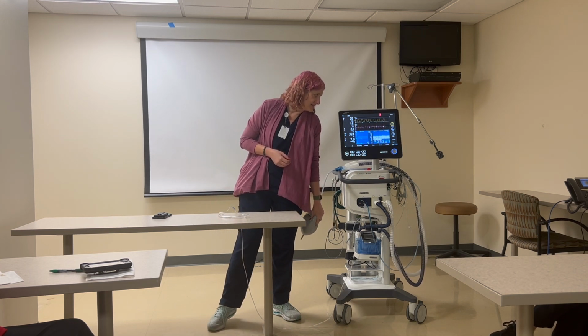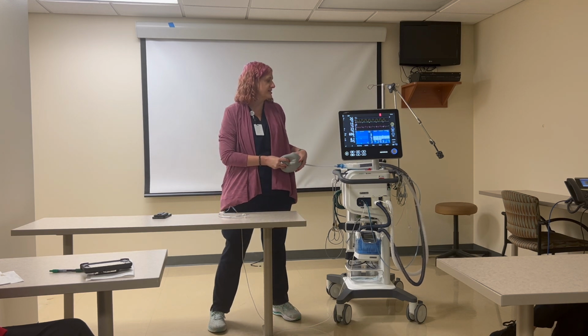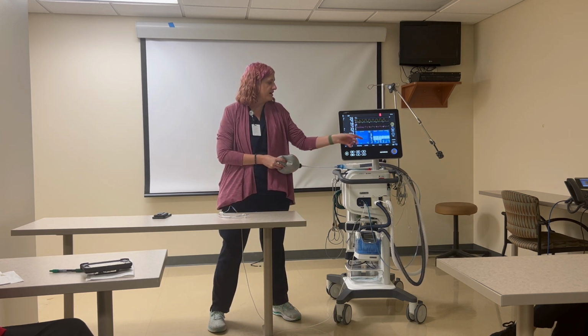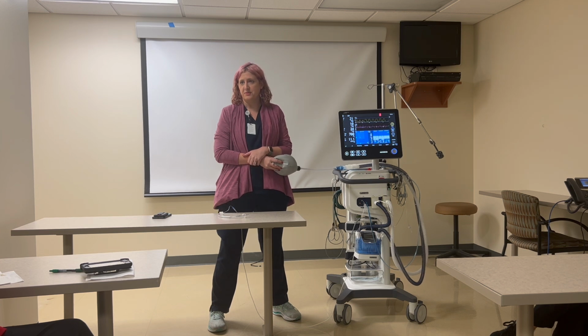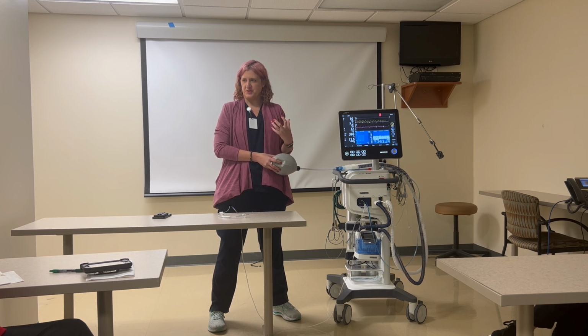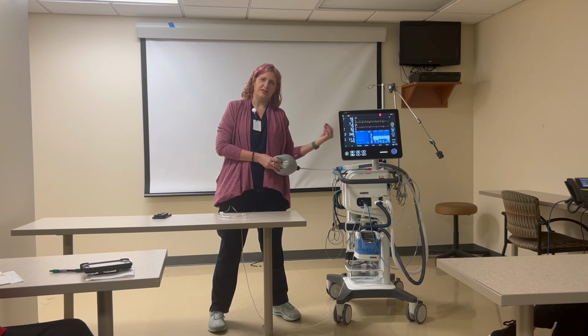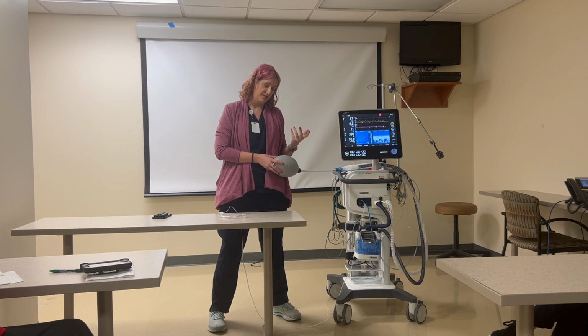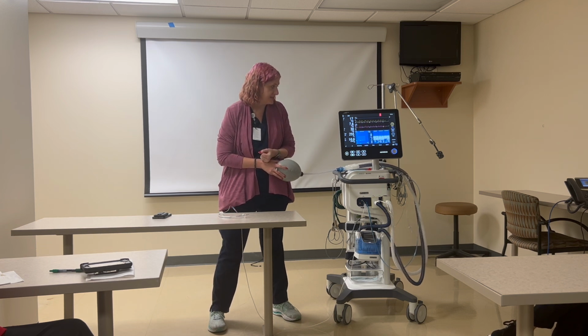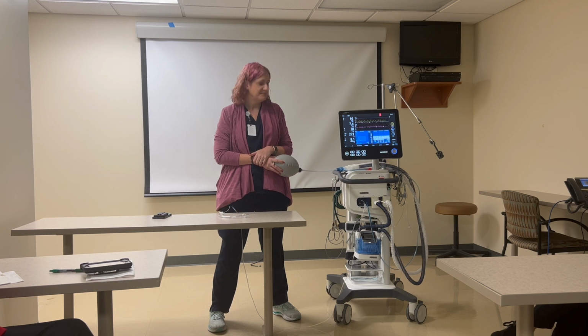The benefit of ASV is once our patient begins to spontaneously breathe, the ventilator is going to back off on that mechanical rate, and it's going to allow the patient to dictate their own ventilation. This allows us to get our patients off the ventilator very fast. And with you guys, I don't know if you do breathing exercises while you're doing therapies, but ASV will allow the patient to breathe in whatever pattern they see fit. So they get a little more control with this versus being in other modes where the ventilator is more demanding, telling them how to breathe, and it alarms a lot more. ASV, as you guys can see, hasn't alarmed yet on us.